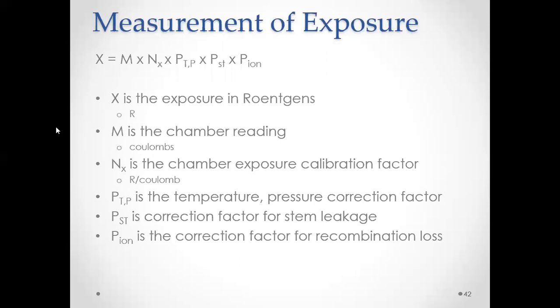Finally, the measurement of exposure involves multiplying several factors together: the chamber reading, the chamber exposure calibration factor, the pressure and temperature correction factor, the correction factor for stem leakage, and the correction factor for recombination loss. Multiplying all of these together gives the exposure.